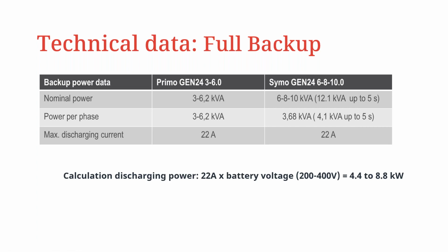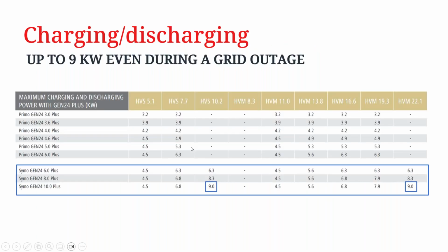So, a calculation of the discharging power. This is when you use your 22 amps multiplied by your battery voltage, either the HVM or HVS. This can be anywhere from 200 all the way to 400 volts, which gives you a value of 4.4 to 8.8 kilowatts. So, charging and discharging up to 9 kilowatts even during a grid outage. This is just stating your maximum of discharging and charging of the HVM or HVS batteries along with the inverter capability. For example, on the Fronius Symo Gen 24 10 Plus, we can see that the maximum is 9 kilowatts with the HVS. And then with the 22.1 HVM batteries, we can also achieve the 9 kilowatts.